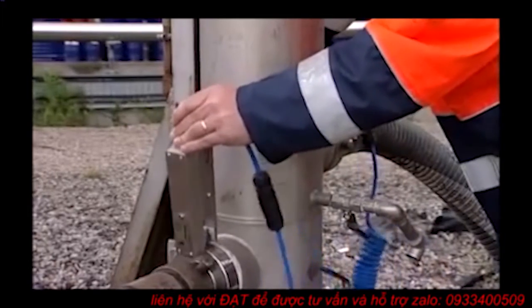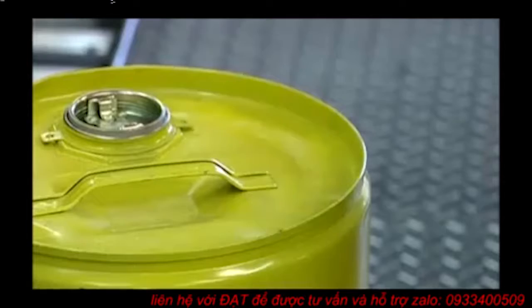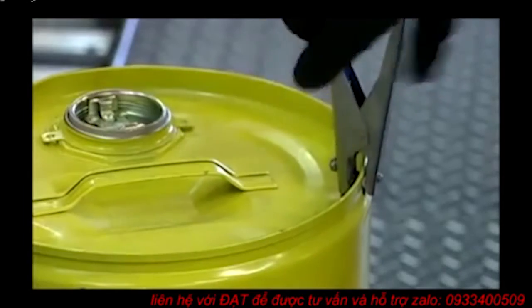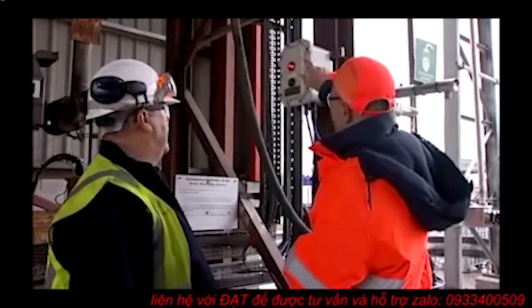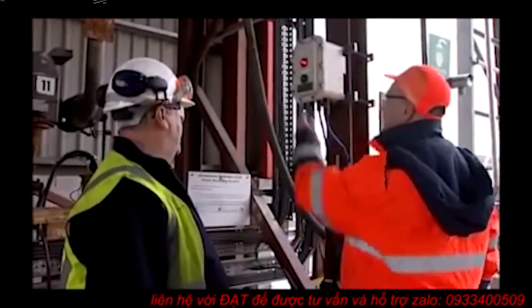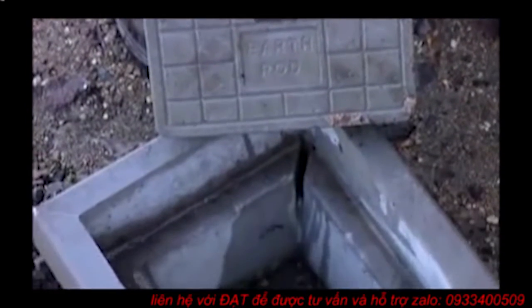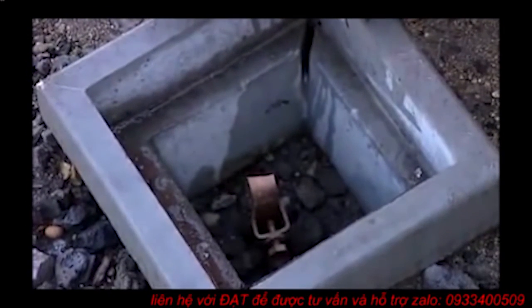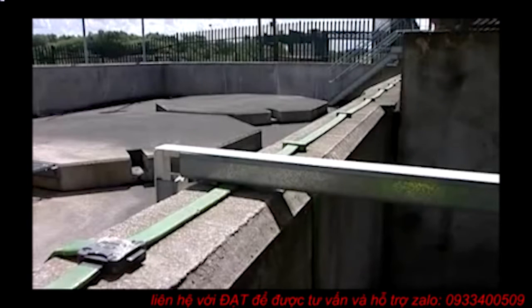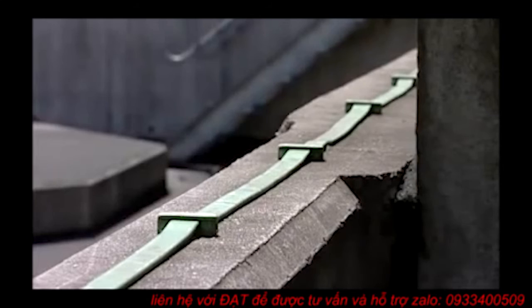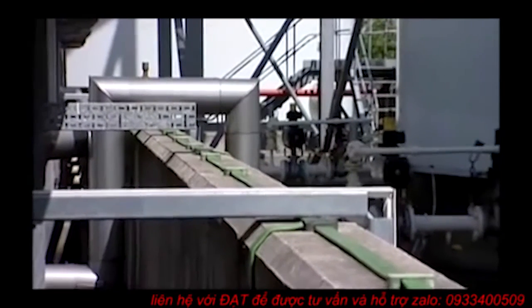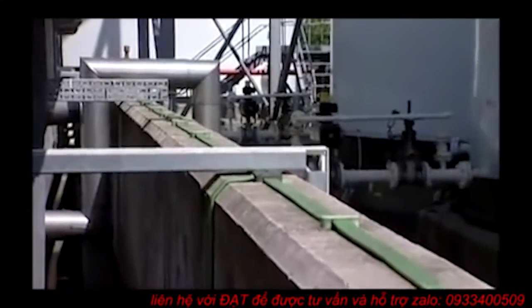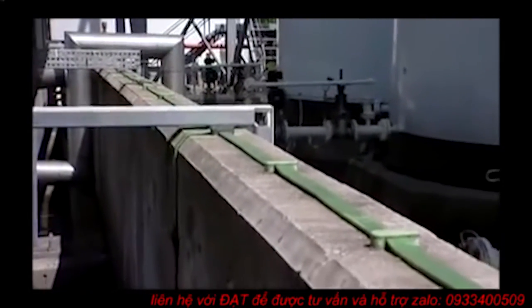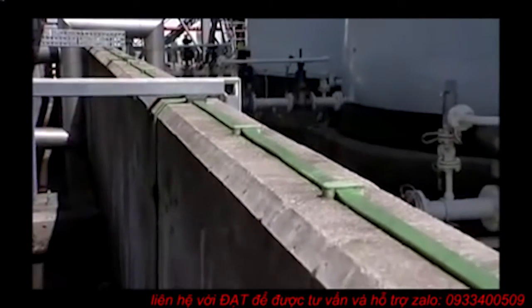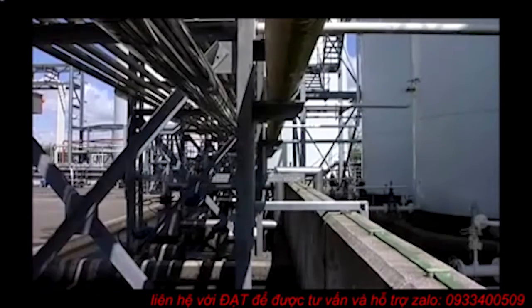To ensure a high level of static electricity awareness is maintained, there should be regular testing of equipment with results logged, frequent awareness training of operators, and reference to the appropriate standards. The fixed part of the earthing system, the earthing rods, the earthing loop, and bonding on fixed equipment, should be tested periodically, usually by a specialist, often in conjunction with tests on lightning protection equipment. A typical test period would be 11 or 13 months, testing during different seasons, and would look for any significant variation from previous tests, indicating deterioration.